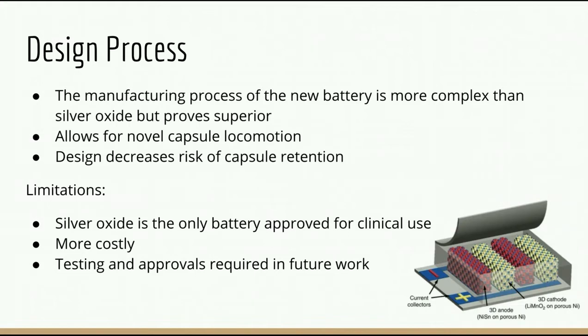The design is expected to remain a size that will be able to safely pass through the esophageal and intestinal tract, as well as power the endoscope and a propulsion mechanism for a period of at least 8 hours. This new design should also reduce the inherent risk of retention because of the locomotion capability. It will be able to dislodge itself better than the previous passive movement design by the use of legs or vibrations. However, there are limitations to the design that include further costs due to the complexity of lithium-ion microbattery production. Approval and testing limitations will be covered in future work.